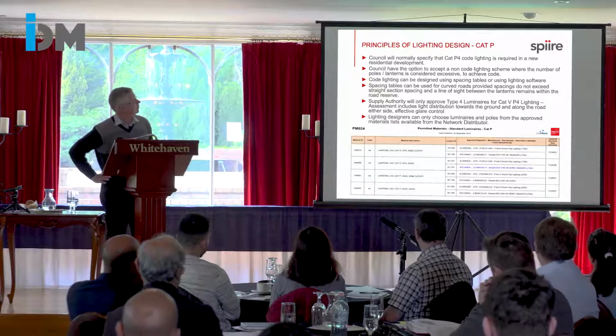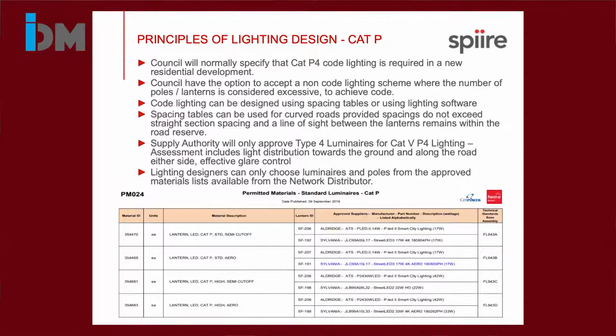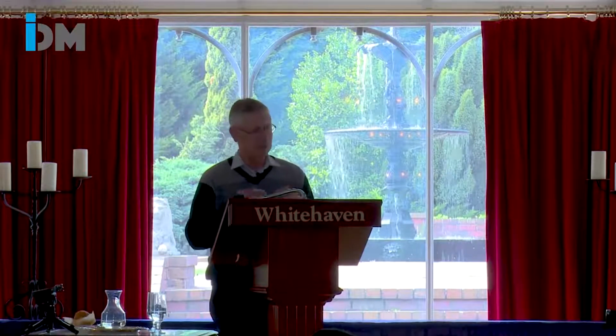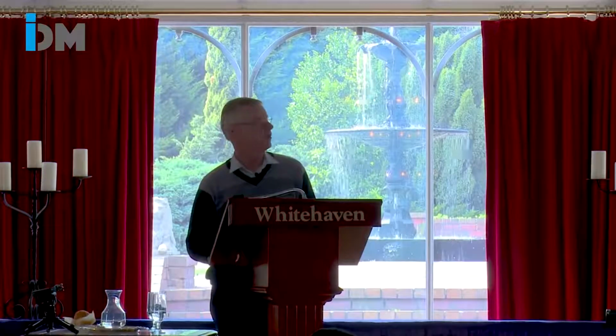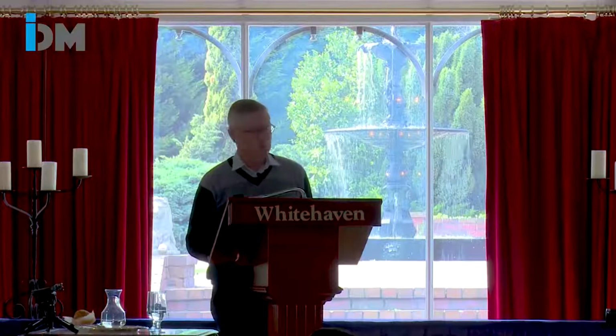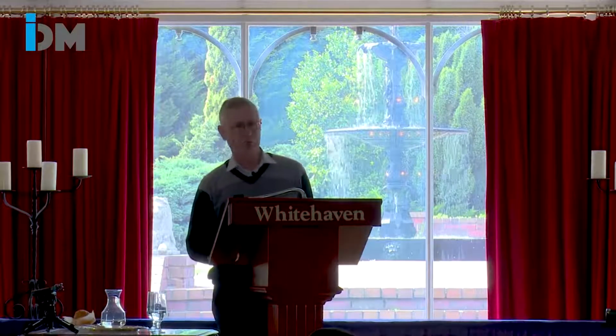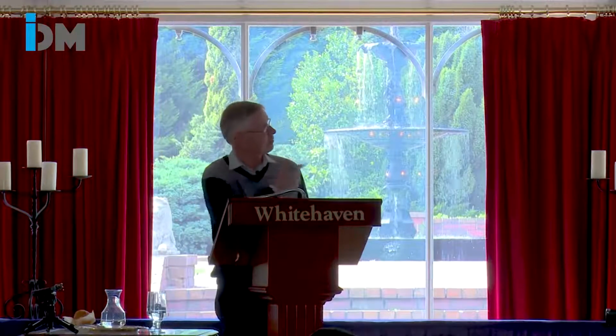So councils will normally specify that a category P4 code lighting is required in a new residential development. Having said that, councils also have the ability to vary that. There are certain situations or certain developments where category P4 is potentially not really relevant or is overzealous. A typical example is your 2,000 square metre lot type developments, where potentially you would have a streetlight pole in front of every block on one side of the road to meet P4 code.